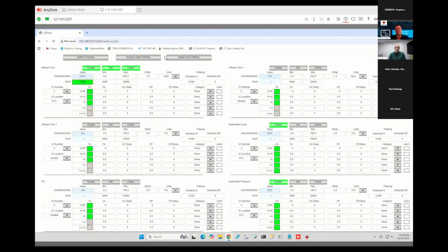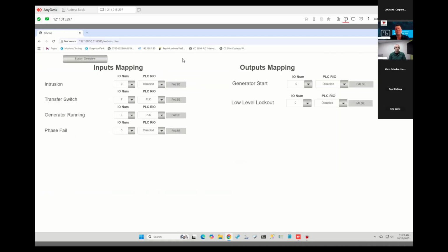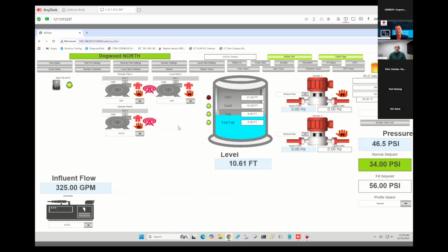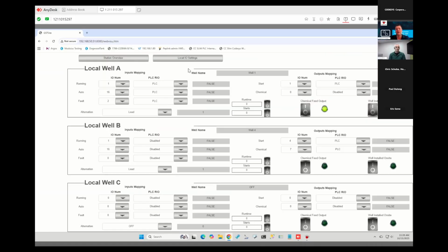And then even to station IO, so your digital inputs, you can map everything here. So if I don't have an intrusion, it's just disabled. It doesn't matter. It won't look at it. And part of what the programming for this went into is, when you look at a local well, if you don't have an auto or you don't have a running signal, if it's disabled, the code itself knows I don't care to look for a running.